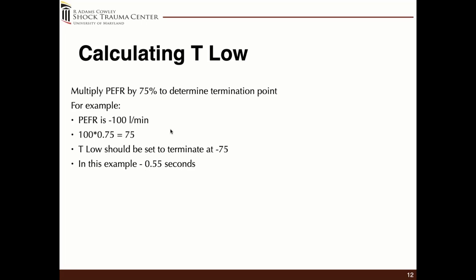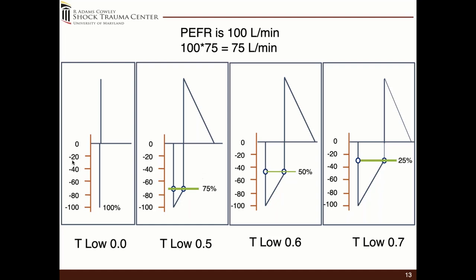Calculating the T low: an easy marker for the adult population is to start with 0.5 — anywhere from 0.4 to 0.6 — then calculate where you need to be. The easiest way is to take your peak expiratory flow rate, the fastest flow coming out of the lung, and multiply by 75%. Your target should be at that 75% level. For example, if the peak is 100 liters, you should target 75 liters as your termination point.